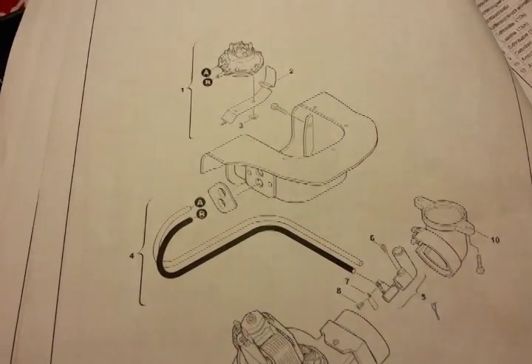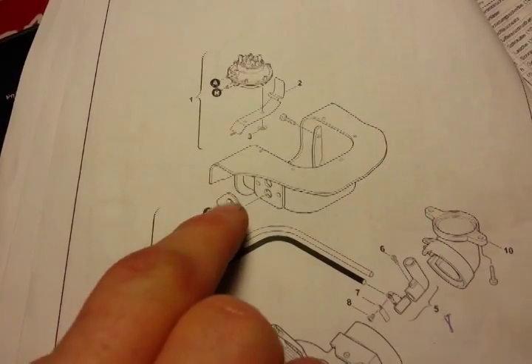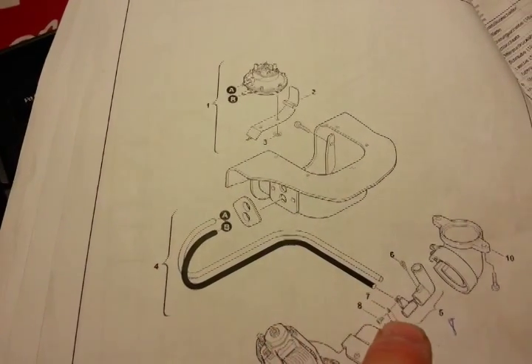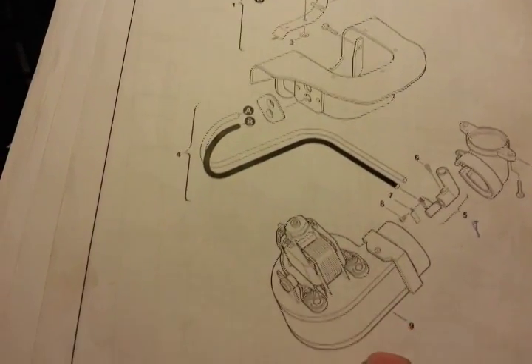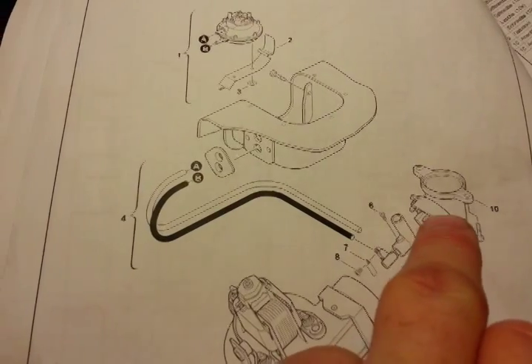it can be a good idea to check for moisture in the system, especially in the hoses to the pressure switch that is measuring that the exhaust is okay. It can be necessary to remove the blower for cleaning the exhaust pipe. There can be a lot of moisture in it.